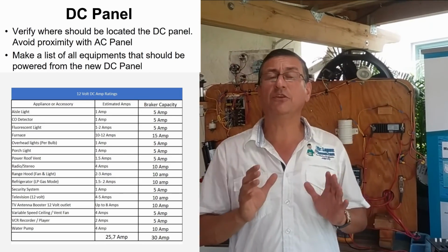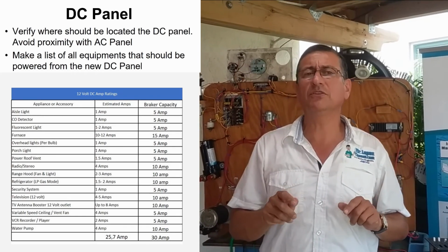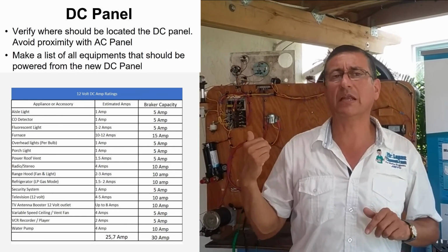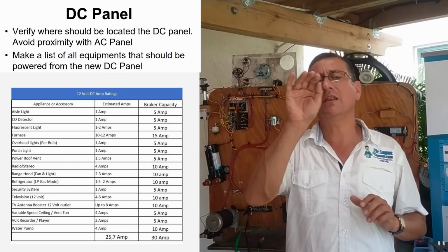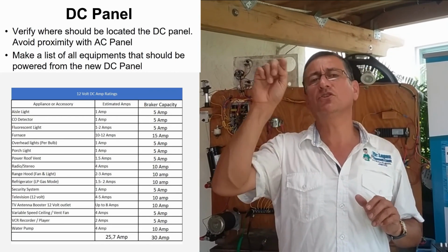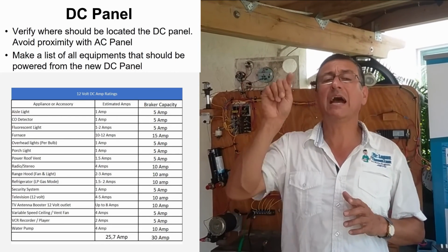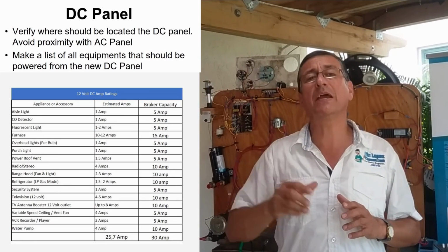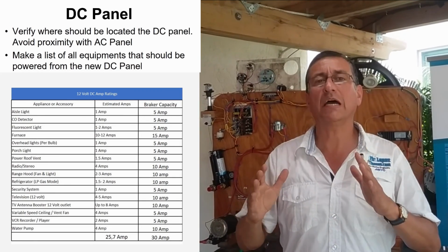You need to make a table similar to the one you have on the screen right now, with the name of the equipment and the consumption in amps per hour. According to that, you select the breaker recommended for that equipment.